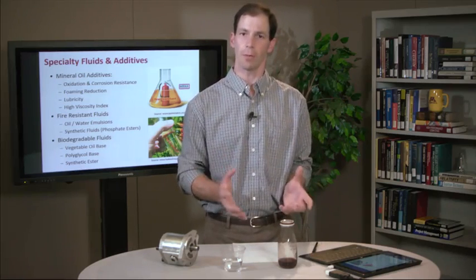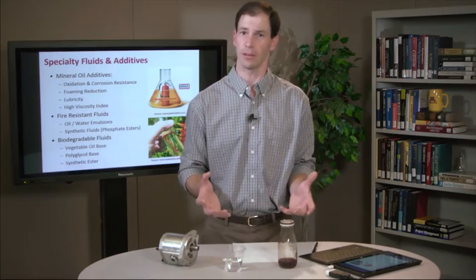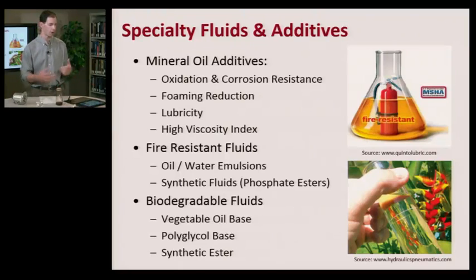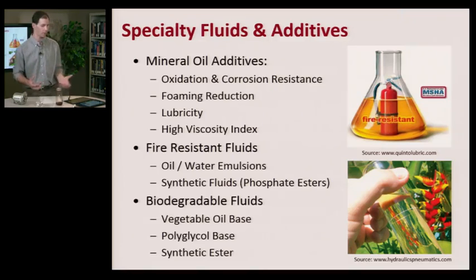Now if a mineral-based oil is not the ideal choice, well other options are to go to some fire resistant fluids where we start to add water to the fluids and so we might have some emulsion of water and oil or oil and water and those mixtures reduce the flammability hazard. Another option for reducing the flammability hazard is looking at some synthetic fluids such as a phosphate ester.